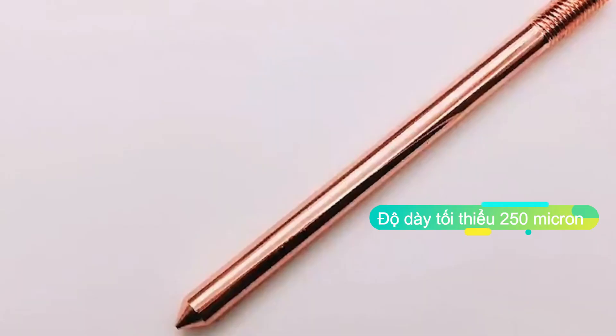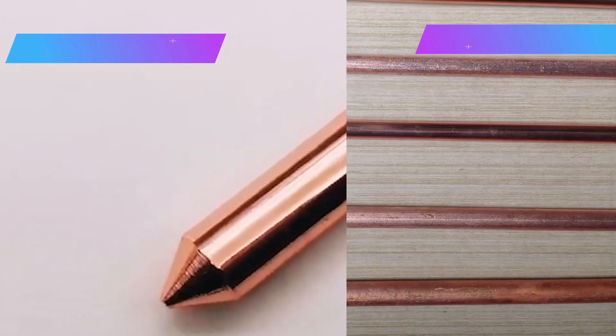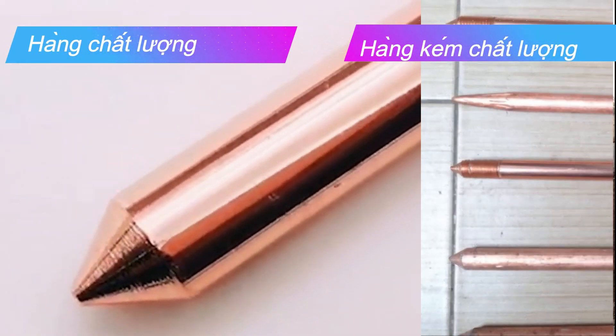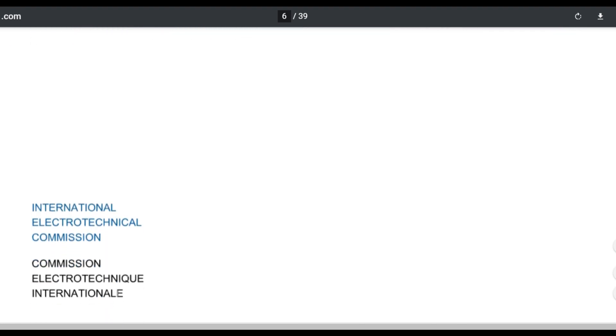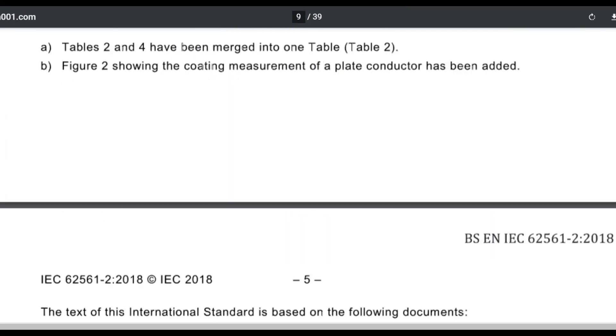Cọc tiếp địa bằng thép mạ đồng có loại nhập khẩu và loại sản xuất trong nước bởi các công ty sản xuất uy tín. Cọc tiếp địa thép mạ đồng phải mạ theo tiêu chuẩn UL 467 và IEC 62561, là tiêu chuẩn của Ủy ban Kỹ thuật Điện Quốc tế IEC. Độ dày lớp mạ trung bình là 254 micron. Khi bẻ một góc 30 độ, lớp đồng không bong chóc. Cọc tiếp địa thường có đường kính 14mm, 16mm, 18mm và độ dài 2400mm. Với các cọc tiếp địa không rõ nguồn gốc, không đảm bảo độ dày lớp mạ sẽ làm cho tính dẫn điện bị hạn chế và không đủ điều kiện để thoát sét với điện thế hàng trăm triệu vôn.